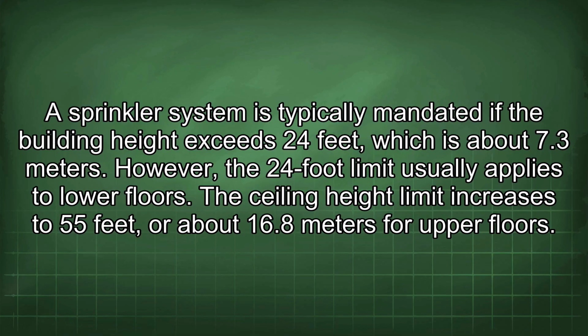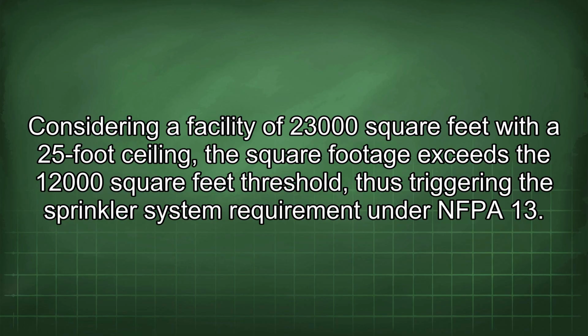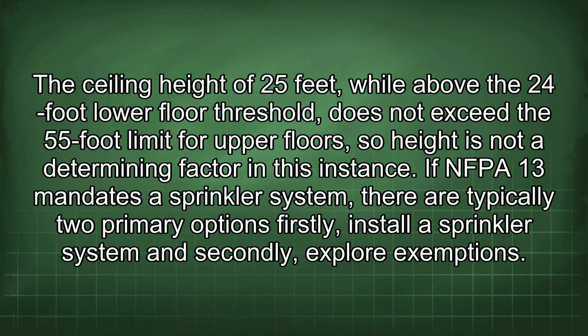However, the 24-foot limit usually applies to lower floors. The ceiling height limit increases to 55 feet, or about 16.8 meters, for upper floors. Considering a facility of 23,000 square feet with a 25-foot ceiling, the square footage exceeds the 12,000 square feet threshold, thus triggering the sprinkler system requirement under NFPA 13. The ceiling height of 25 feet, while above the 24-foot lower floor threshold, does not exceed the 55-foot limit for upper floors, so height is not a determining factor in this instance.